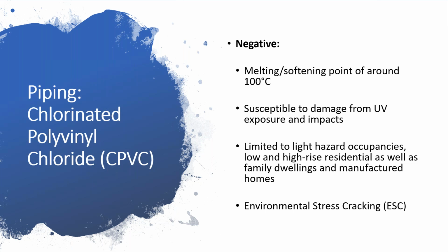In Canada, it is limited to light hazard occupancies, so low and high-rise residentials, as well as family dwellings and manufactured homes, as opposed to steel piping that can be used in industrial applications. One important failure mechanism is that it is subject to environmental stress cracking, which is a failure mode that is very hard to detect in its early stages, and we find it when it's too late and it starts leaking.